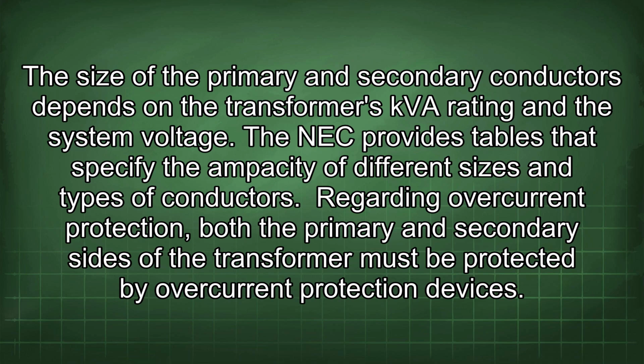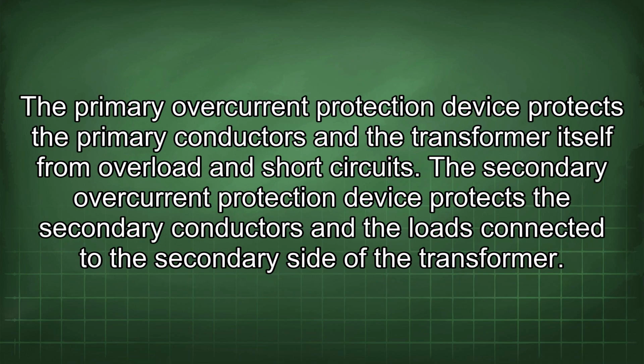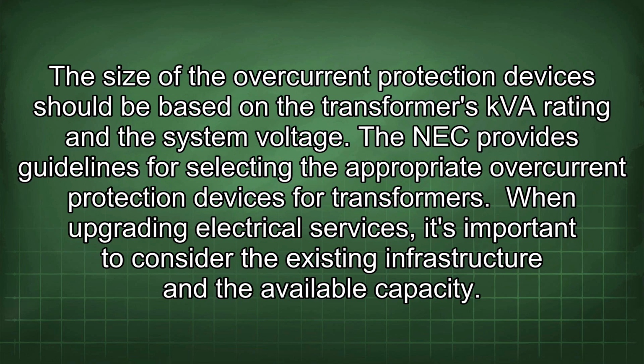Regarding overcurrent protection, both the primary and secondary sides of the transformer must be protected by overcurrent protection devices. The primary overcurrent protection device protects the primary conductors and the transformer itself from overload and short circuits. The secondary overcurrent protection device protects the secondary conductors and the loads connected to the secondary side of the transformer. The size of the overcurrent protection devices should be based on the transformer's kVA rating and the system voltage. The NEC provides guidelines for selecting the appropriate overcurrent protection devices for transformers.